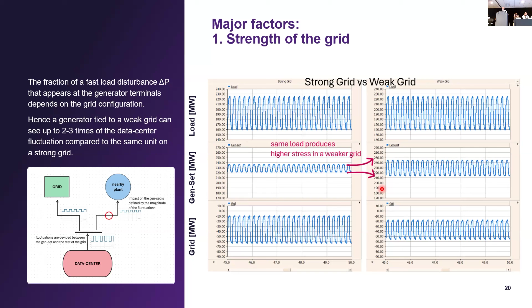And we found out there are three major factors which impact how much of the stress is actually seen by the generator terminal. Factor number one is probably the most obvious: electrical split of impedance. Basically, how electrically close the machine is to the source. If we look from the data center perspective into the grid and into the nearby plant, the load will be proportionally distributed between the generator and the grid. And if the grid is weaker, meaning it has a large impedance, more of this stress will be seen by the generator and less by the grid. If we take an extreme example, an off-grid island type of situation, 100% of this load will be consumed by the generator. So this is factor number one.